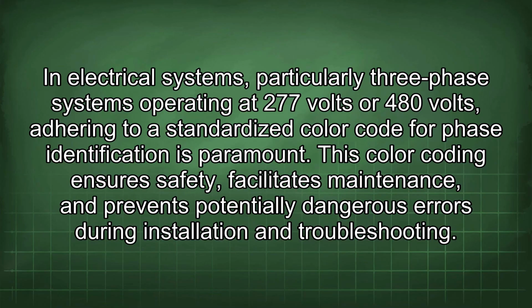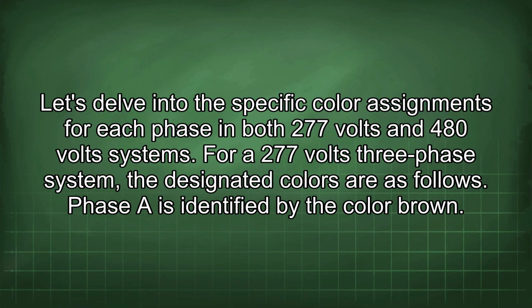In electrical systems, particularly three-phase systems operating at 277 volts or 480 volts, adhering to a standardized color code for phase identification is paramount. This color coding ensures safety, facilitates maintenance, and prevents potentially dangerous errors during installation and troubleshooting. Let's delve into the specific color assignments for each phase in both 277 volts and 480 volts systems.